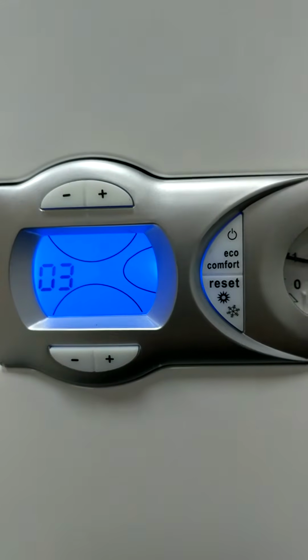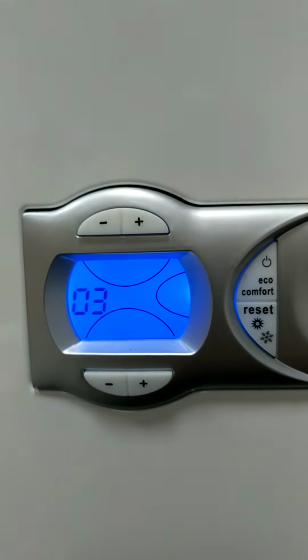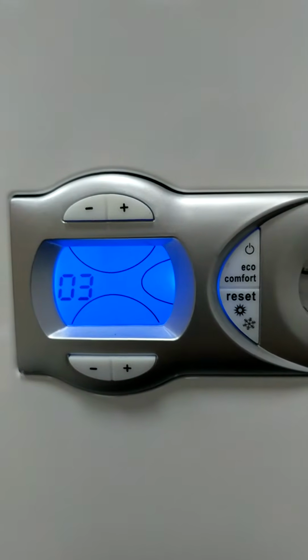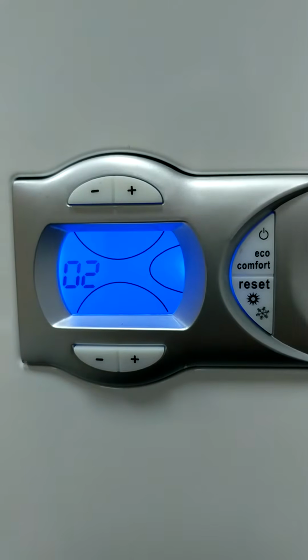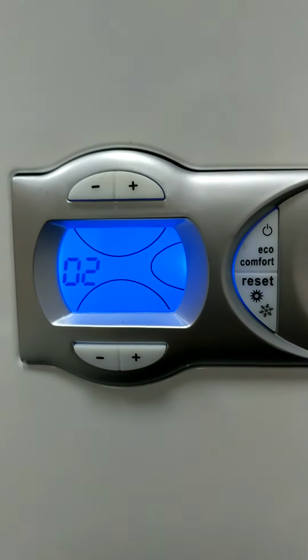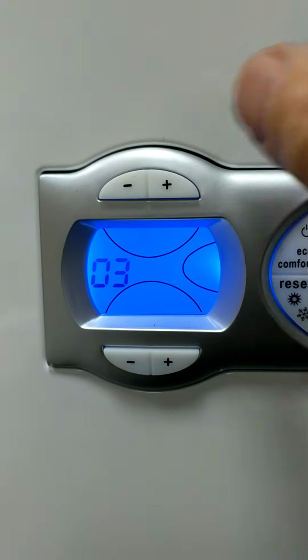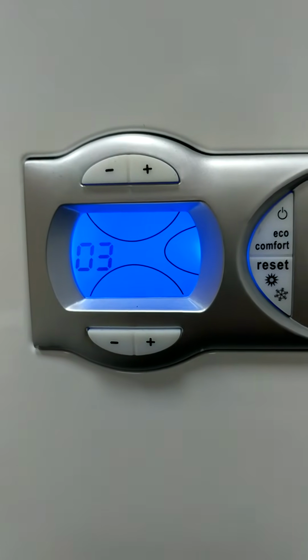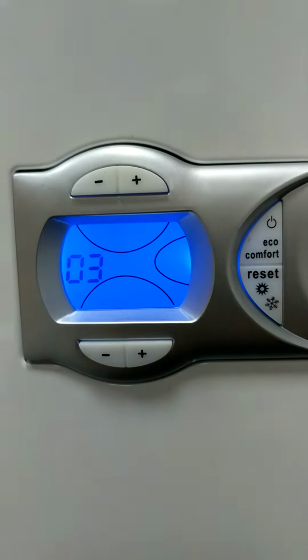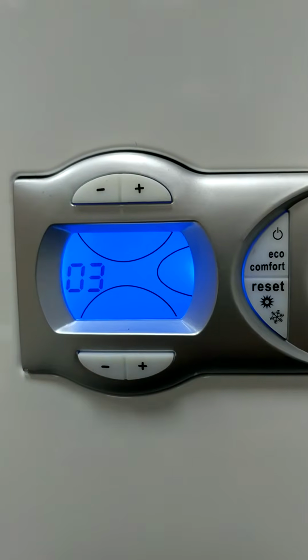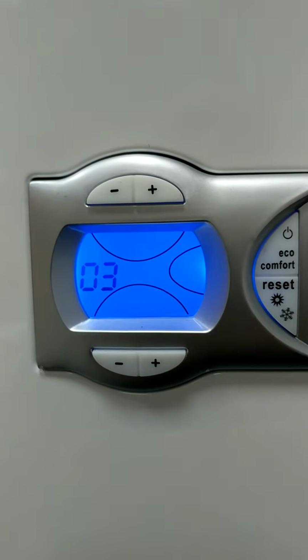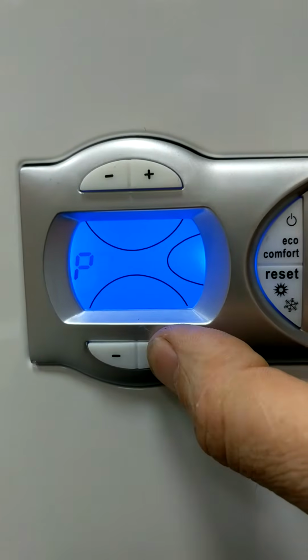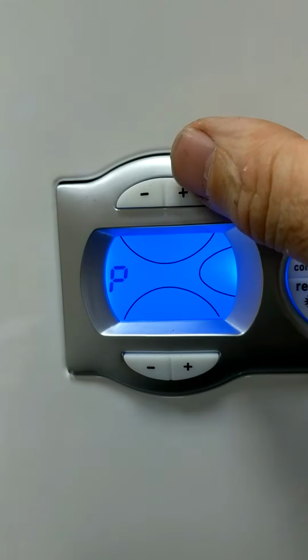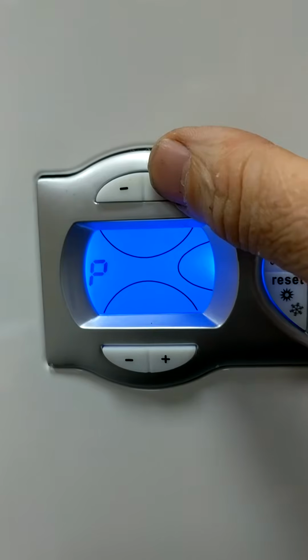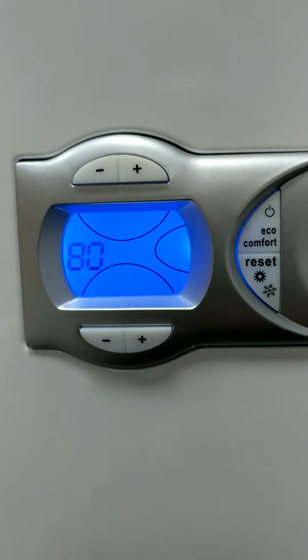The ramp rate is how fast you want these radiators to heat up. Now up to about 6 radiators, you keep it on about 2 degrees every minute. Anything over 6 radiators, you knock it up to 3. And that's the ramp rate, and that's how fast you want the radiator to heat up. Then we'll go on to parameter 5, and this is the actual temperature, the actual set temperature.